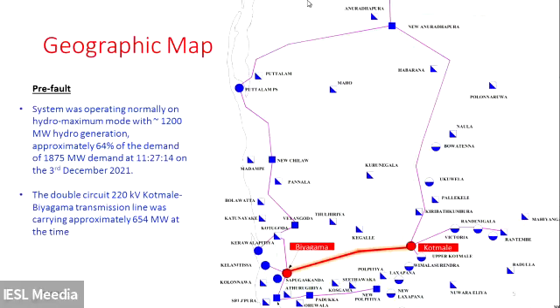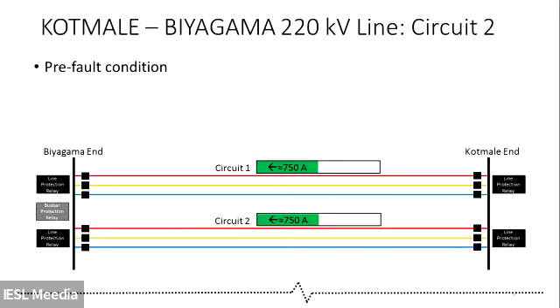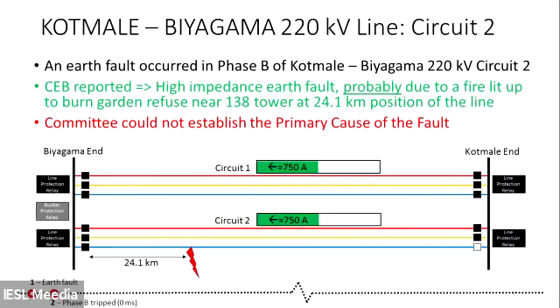The line locations are given here. This 650 turns out to be 750 amperes in terms of current, and this was the pre-fault condition. And suddenly in circuit two, there are two circuits, a double circuit line, as the majority of you know. Suddenly at 11:27 and 14 seconds, we could see in the fault recorder diagrams that there is a neutral current increase and phase B current decreasing, which is typical of a high impedance earth fault. It was located 24.1 kilometers from the Biyagama end, near tower 138 in the line.